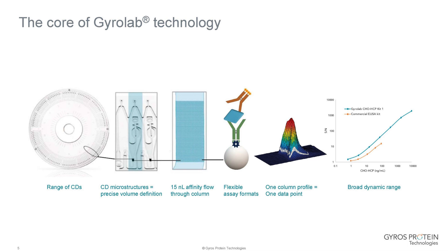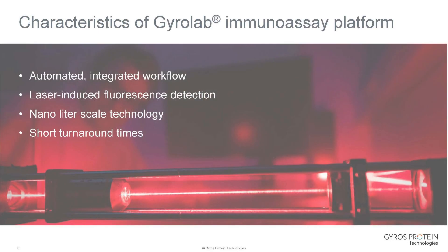Because detection involves laser-induced fluorescence, this gives us good assay sensitivity but also a broad dynamic range. The characteristics of the Gyrolab immunoassay platform include being fully automated with an integrated workflow. Detection via laser-induced fluorescence gives a broad dynamic range and good sensitivity. The volumes are nanolitre scale, saving both reagents and sample, and providing short turnaround times — ideal for assay development, as a full assay takes one hour to perform.